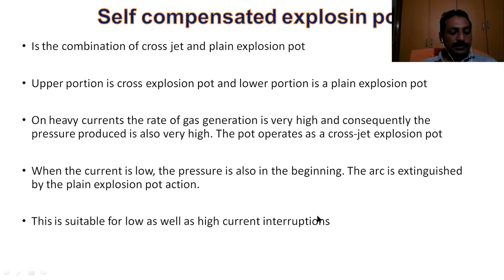If a small current, nothing but a low current, is developed, the strength of the arc is also low, meaning that a small magnitude of arc is developed. Because of that, the pressure is also low at the beginning. The arc is extinguished by the plain explosion pot action. Already we have seen that in the plain explosion pot, oil is simply pumped between these two contacts, so the arc is extinguished. This self-compensated explosion pot type of oil circuit breaker is suitable for low as well as high current interruptions.